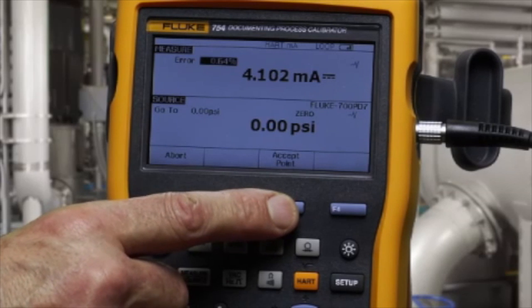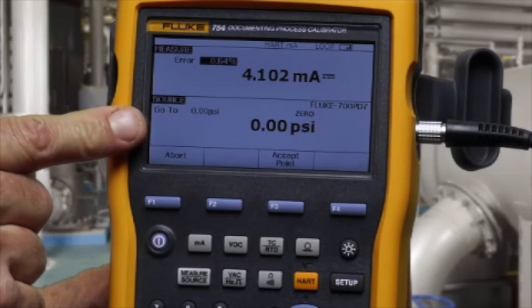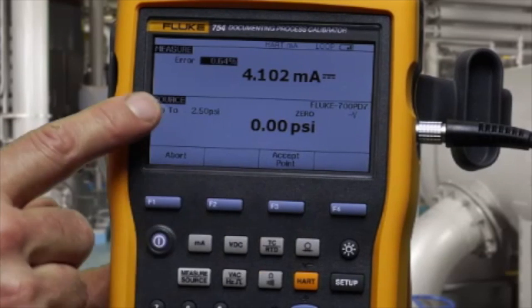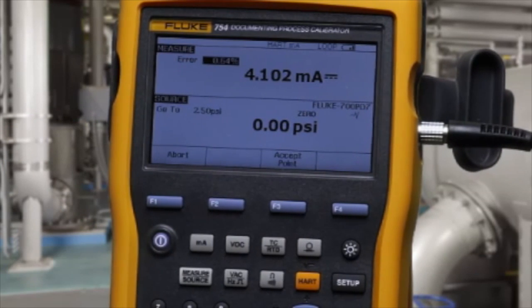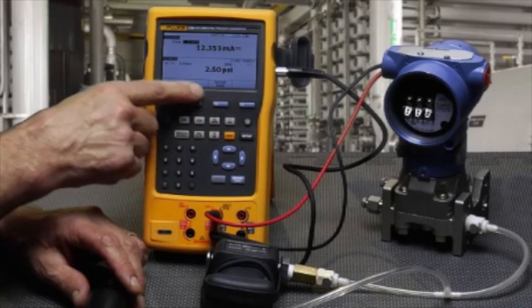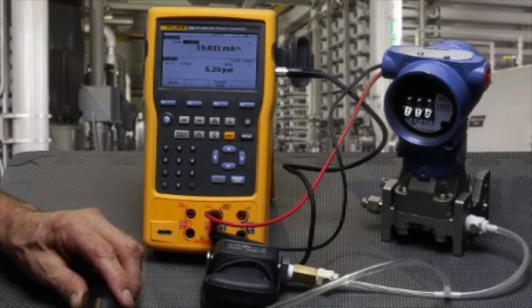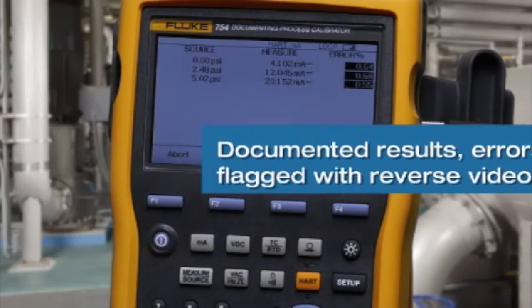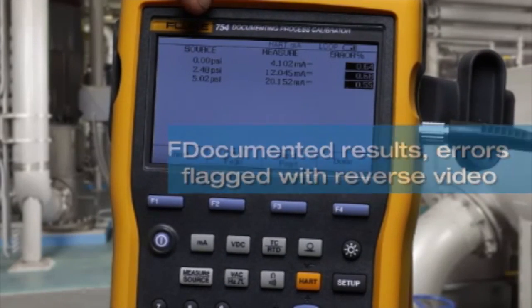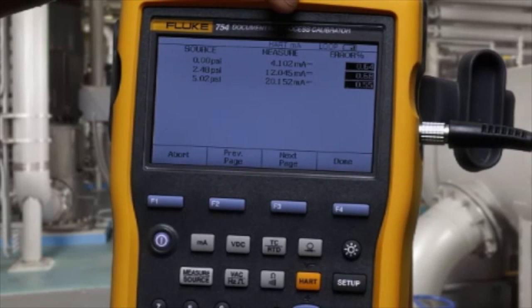Manual test tells us the pressure to apply. Accept. Go to 2.5 PSI. Pump up to 2.5 PSI and accept. And go to 5 PSI and accept. You have the recorded pressure that's applied, the milliamp that's measured, and the error percent of span.